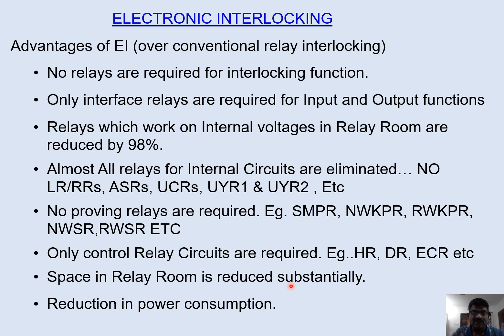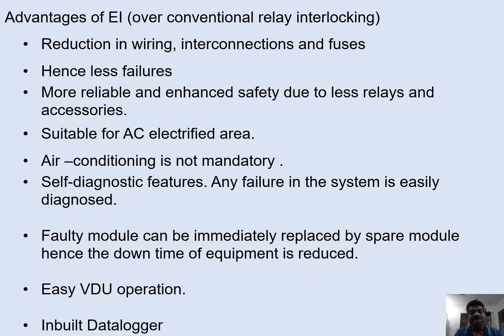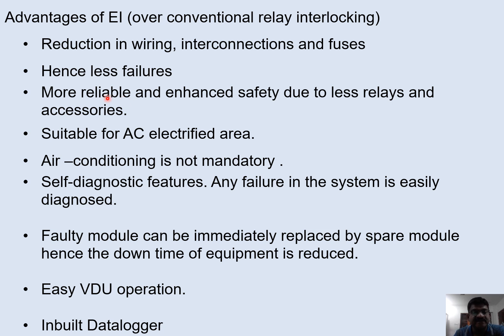Space in the relay room is reduced substantially. As the number of relays has come down, the place requirement has also come down, and there is a reduction in power supply. Reduction in wiring, interconnections, and fuses — because of these reduced relays and wiring, failures naturally come down. At the same time, EI is more reliable: once it is fixed, no one can change it, and interference or shortcuts in EI are not possible. Hence, enhanced safety due to less relays and accessories.